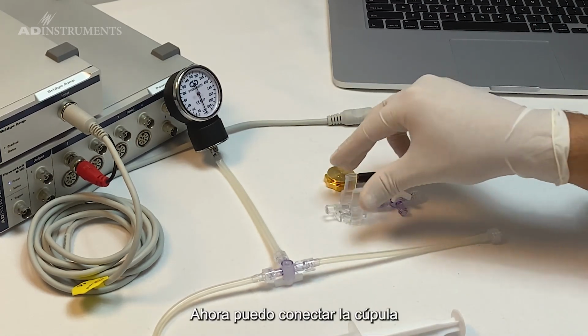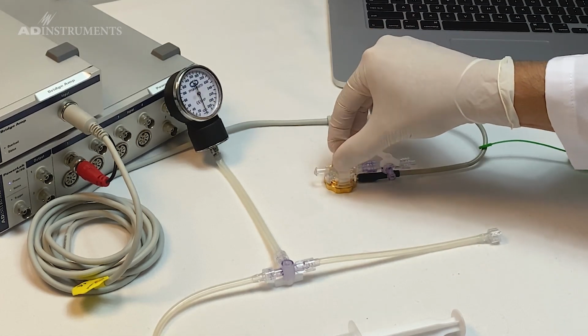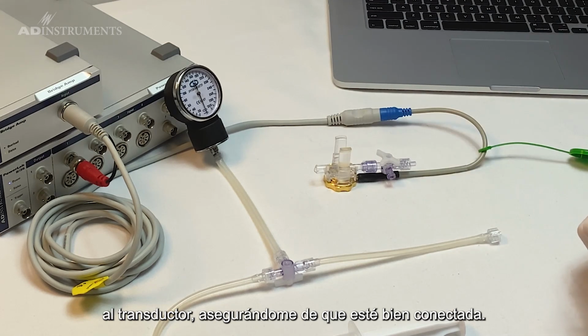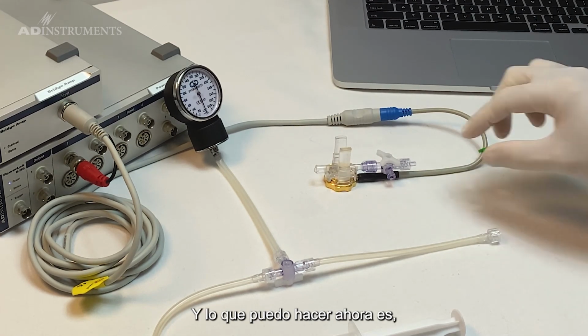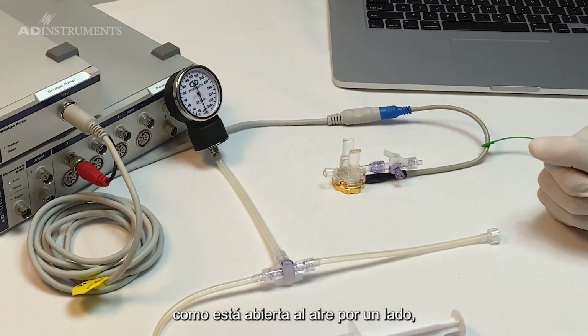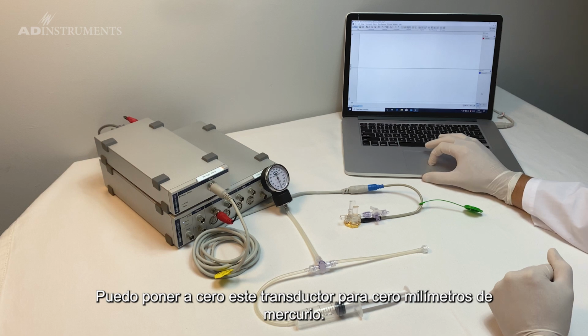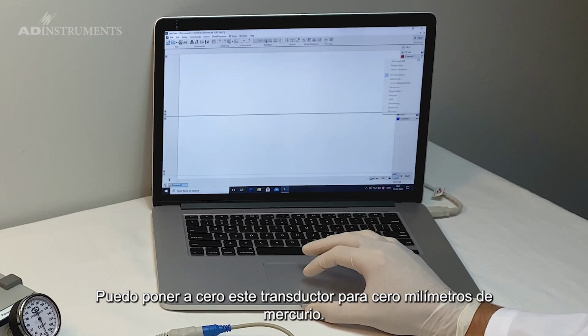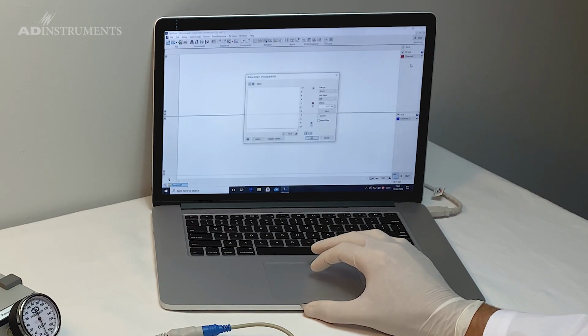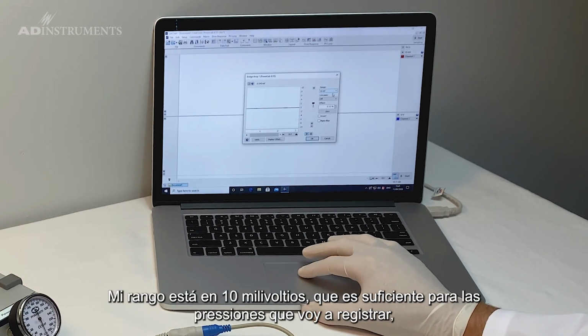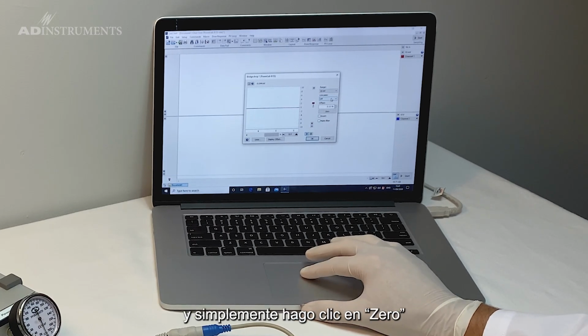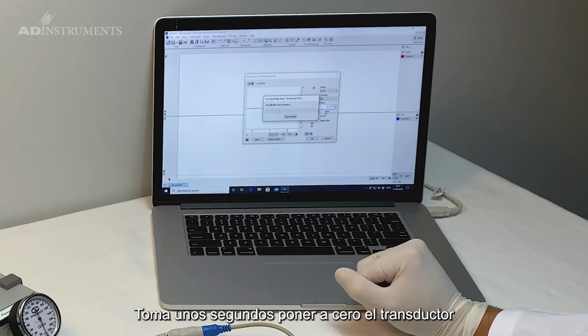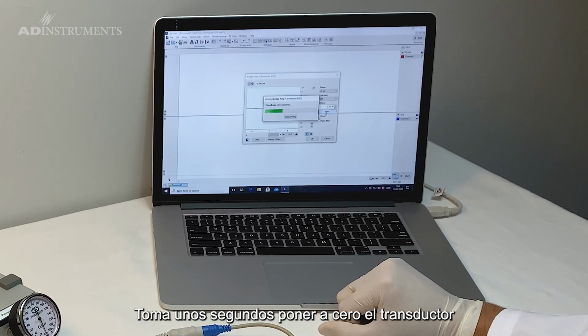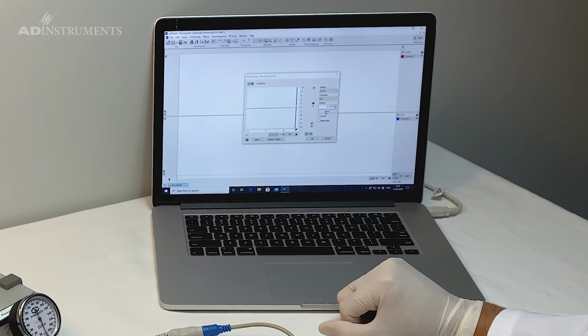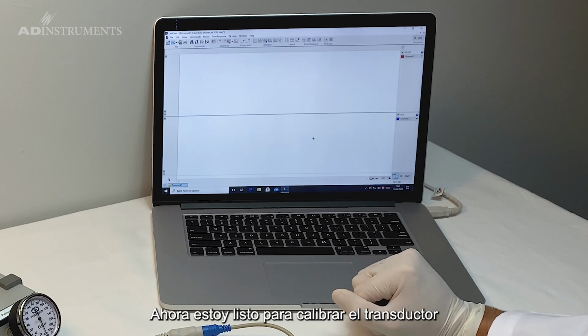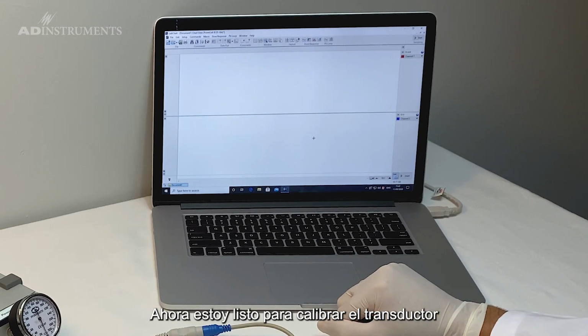I can now attach the dome to the transducer, making sure that it's on. And what I can do now is, because it is open to air on the one side, I can zero this transducer for 0 millimeters of mercury. So I go to the bridge amp. My range is on 10 millivolts, which is sufficient for the pressures I'm going to be recording, and I just click on 0. It takes a couple of seconds to zero the transducer, and I click OK, and now I'm ready to calibrate the transducer.